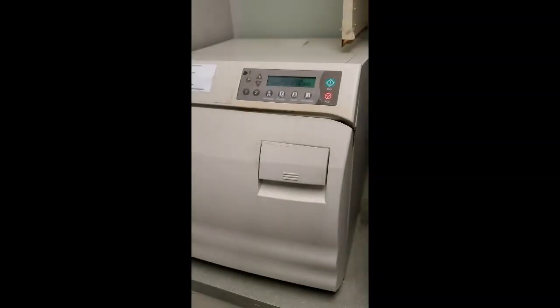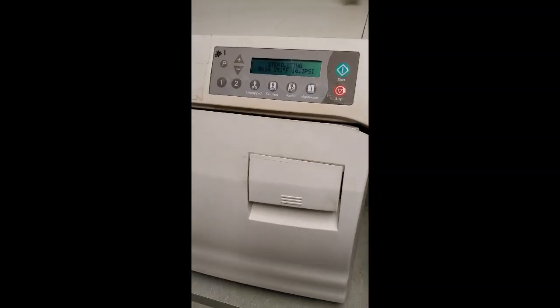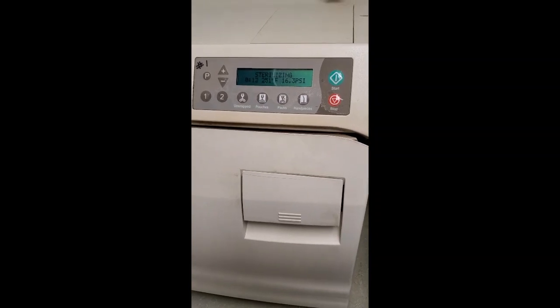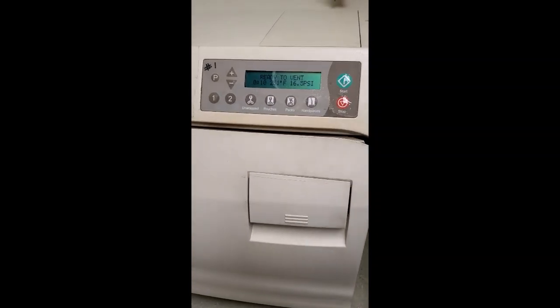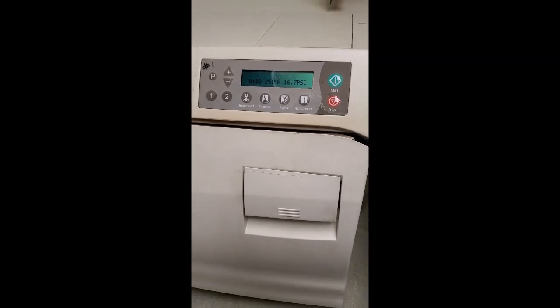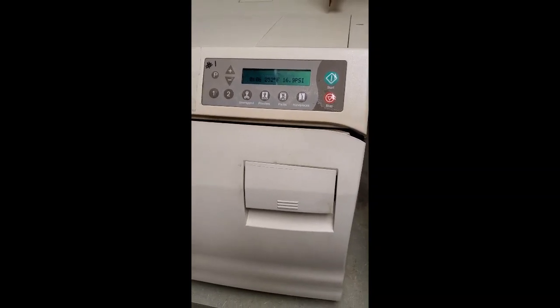All right, so we are back for the next part of our autoclave cycle. So the machine filled with water, it got up to temperature, it got up to pressure, and then it ran a 30-minute sterilization cycle. Let me just show you, we have a few seconds left of that cycle. So you can see that it did get up to the right temperature and the right pressure, so it's going to get ready to vent.